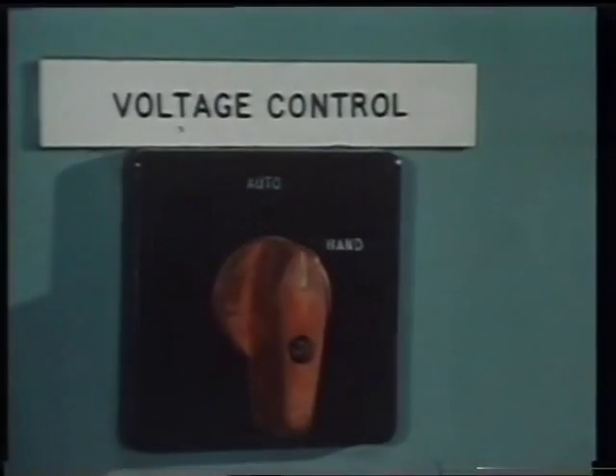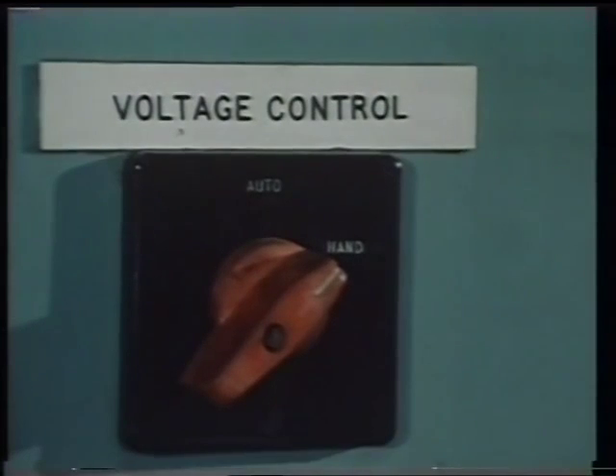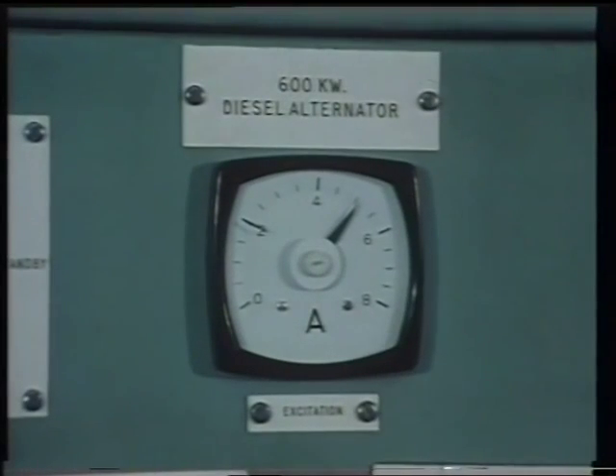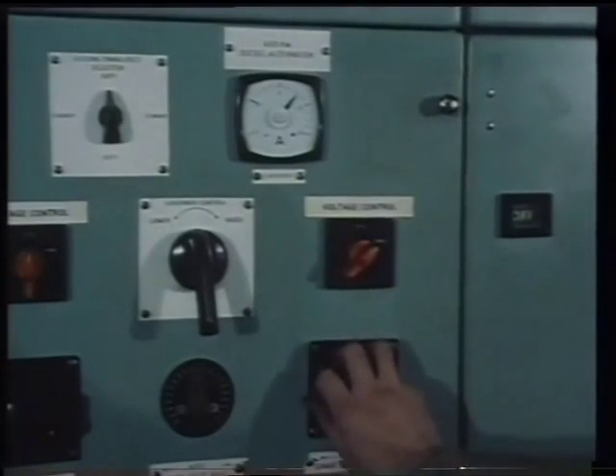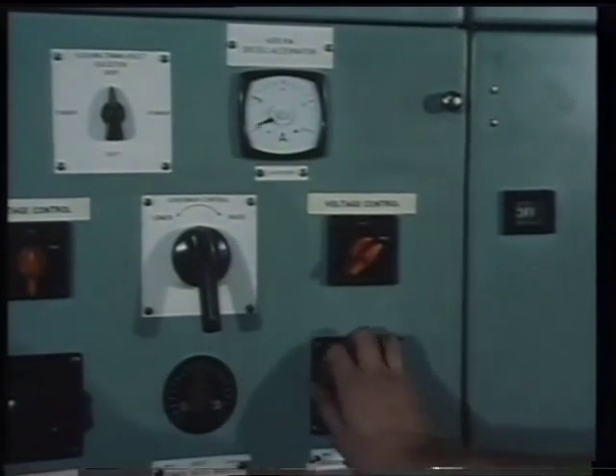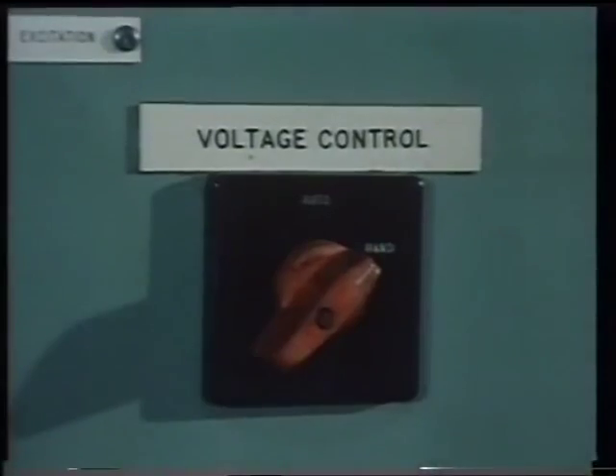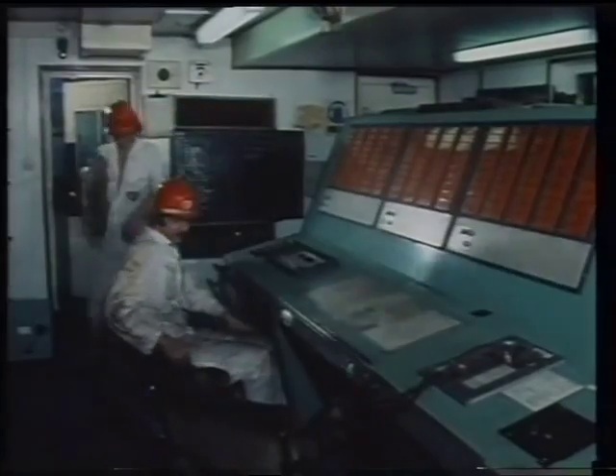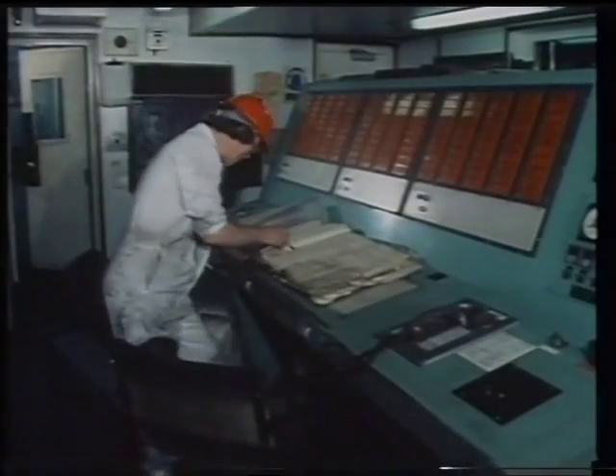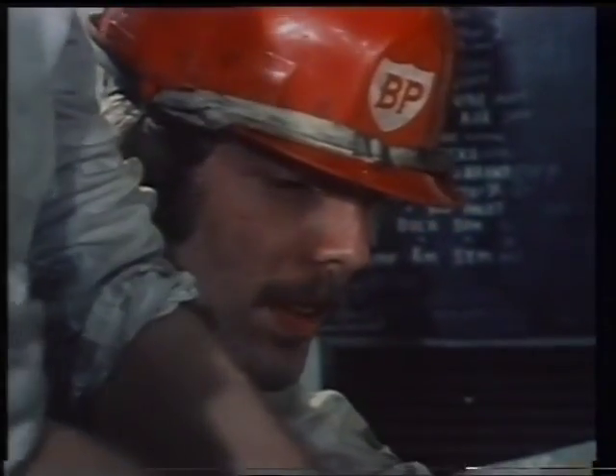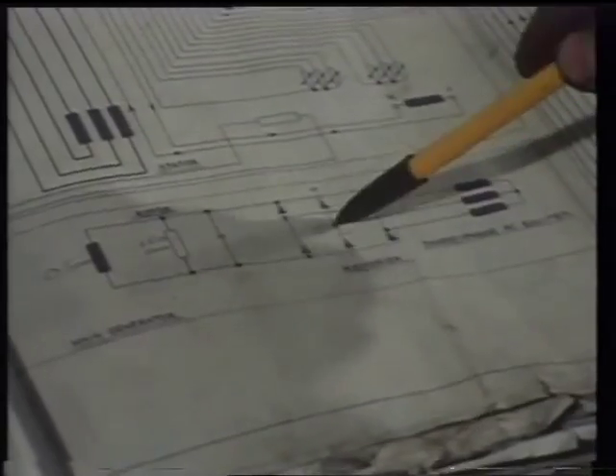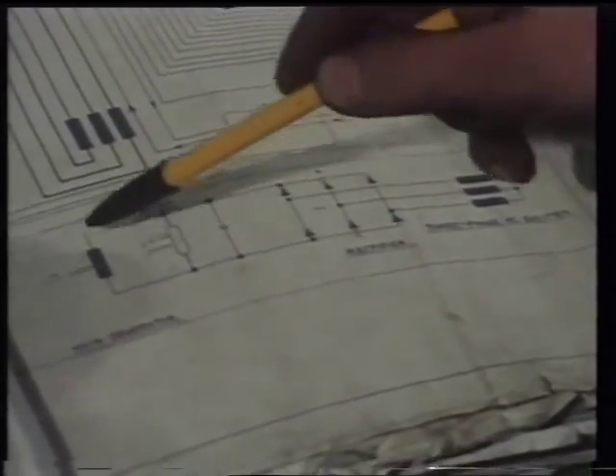So, first switch to manual voltage regulation to see if a fault exists in the automatic voltage regulation. No, the excitation current is just as high and not easily regulated. Shut down the machine and consult the circuit diagram. The output of the exciter goes to the rotor coils through a diode rectifier system, and the coils are in parallel with a diode surge protection system, here made up of a capacitor and a resistor. Their function is to stop any voltage spikes damaging the diodes.